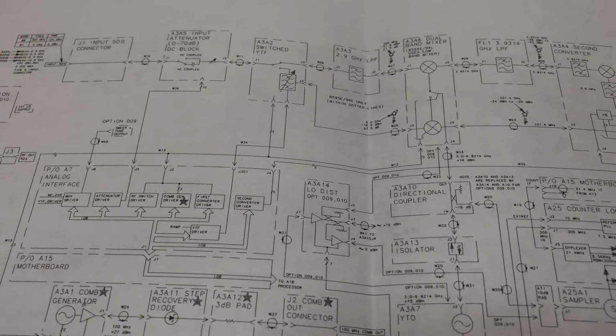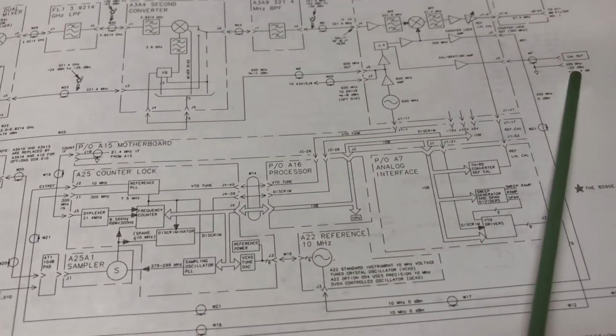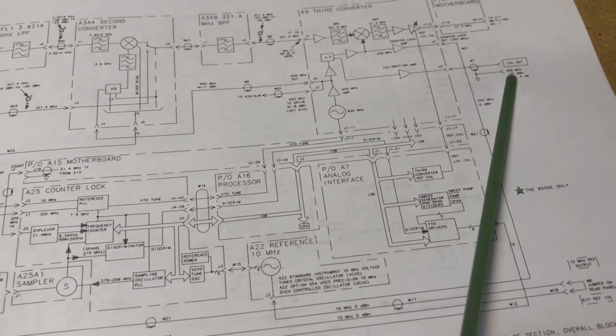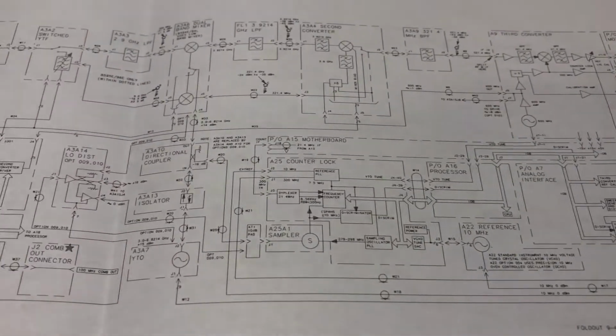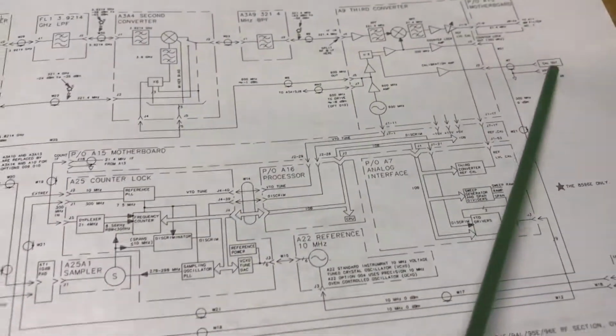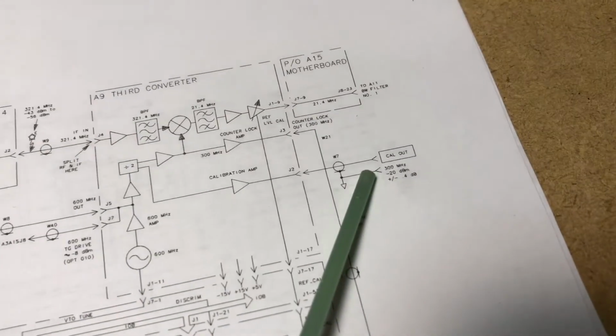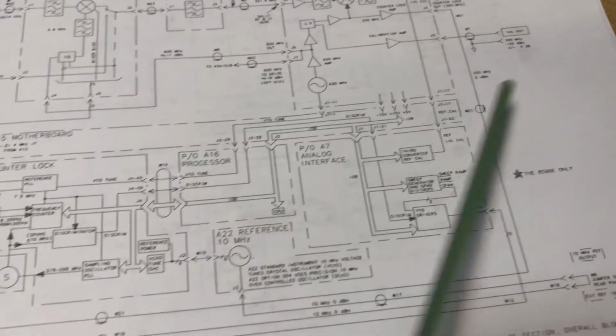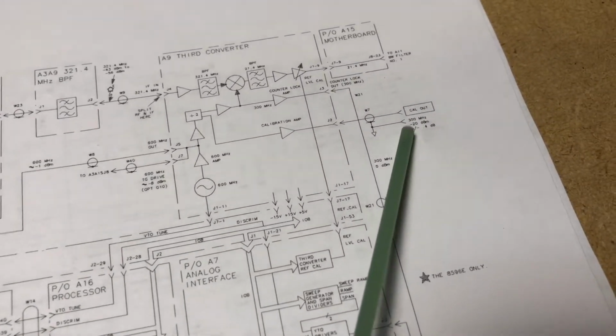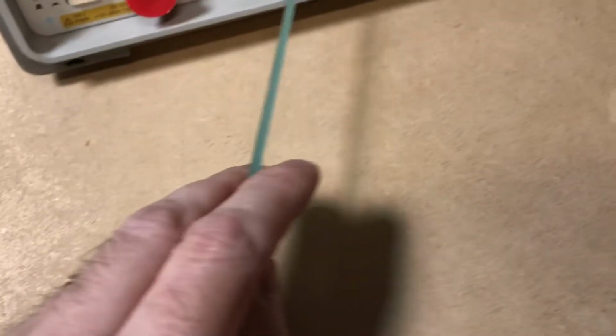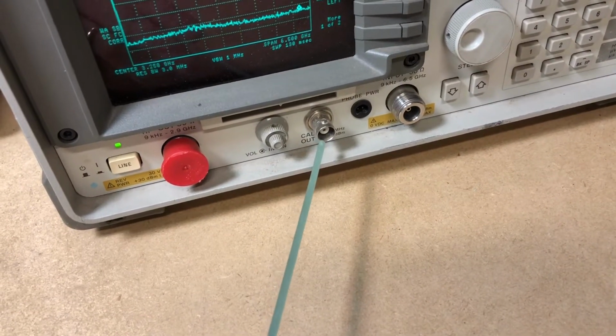The unit has some built-in test functions. The unit uses a lot of DACs, digital analog converter blocks, to basically, essentially what it does is it takes your cal output, which is here, and it uses this as a known reference, and it calibrates this whole chain all the way out to the video output, to give you the best response on the display. So as long as your cal output signal is correct at 300 megahertz and minus 20 dBm, because that's your reference, the unit's going to calibrate itself to that known value. Now I'm pretty confident that the RF output or the cal output signal is good, but we'll check it.